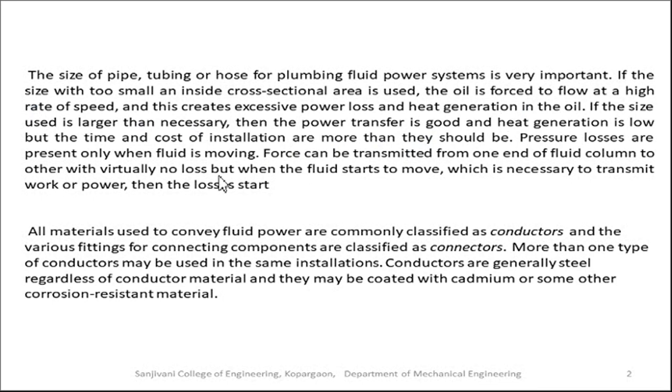And if the size of the conductor which carries the fluid in the fluid power system is more than necessary, then the power transmission will be good and heat generation will be low, but at the same time the cost of installation will go up. So because of all these reasons, the size of the fluid power conductor has to be optimum. That means it should not be too much more or too much less.